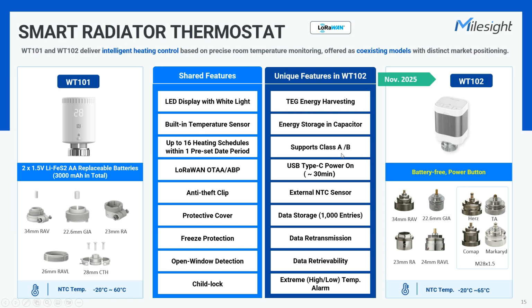If the capacitor ever gets fully depleted, you can easily recharge it. Just 30 minutes of charging via the USB Type-C port will power it on, and a full charge takes about 5 to 6 hours. Another key feature of the WT102 is the support for an external NTC temperature sensor. Since these devices are mounted on hot radiators, the built-in sensor can sometimes be influenced by that heat. But the external sensor lets you get a much more accurate reading of the actual room temperature, which leads to smarter, more efficient control of the hot water flow.